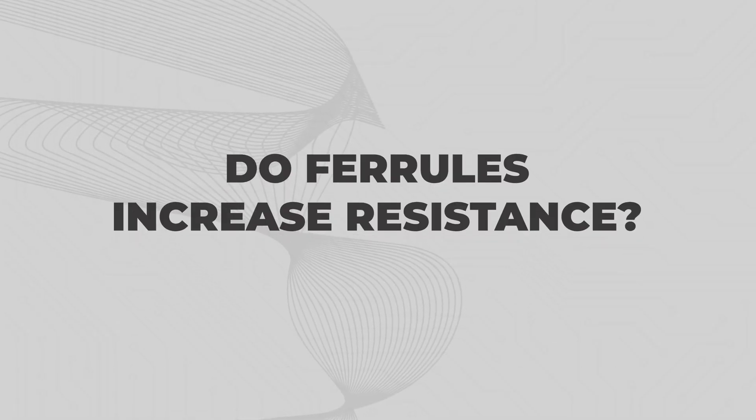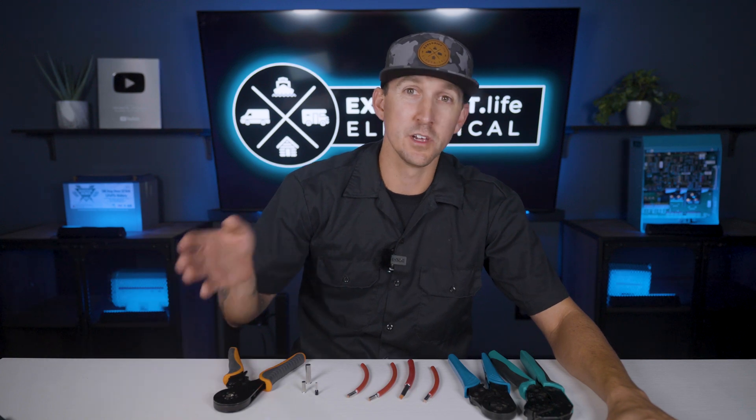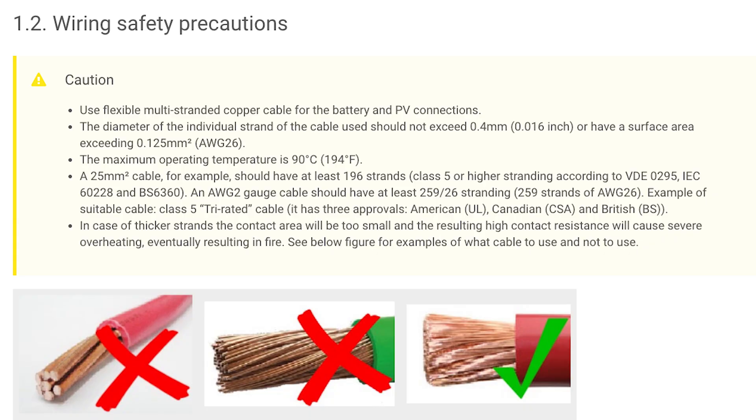Do ferrules increase resistance? Over the years I've gotten some hate for teaching people about ferrules because some people think that ferrules increase resistance and that they shouldn't be used. Specifically citing the Victron Smart Solar user manual on page one where it states: in case of thicker strands, the contact area will be too small and the resulting high contact resistance will cause severe overheating, eventually resulting in fire. What this is saying is to not use solid core wire for a square terminal connection, because this mismatch of shapes will decrease the surface area of the connection, increasing resistance, causing heat and melting.